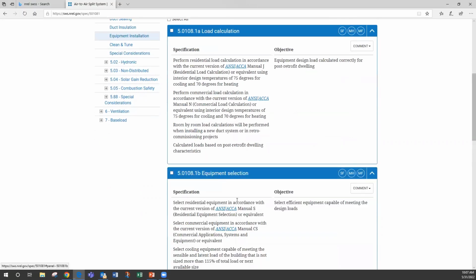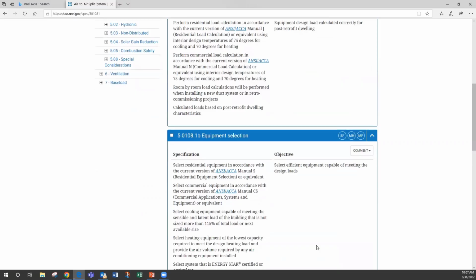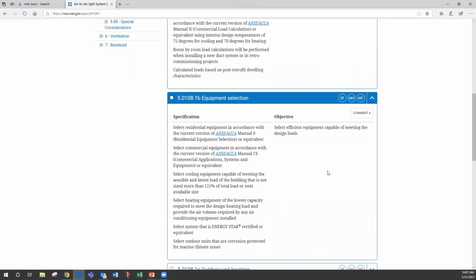Equipment selection. So as far as the SWS under equipment selection, they're telling you to reference the ACCA Manual S process. Another note here, selecting cooling equipment capable of meeting the sensible and latent load that is not sized more than 115% of the total load or the next available size. So keep that in mind. That's ACCA Manual S.